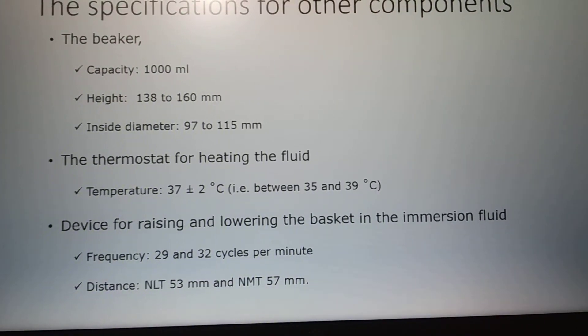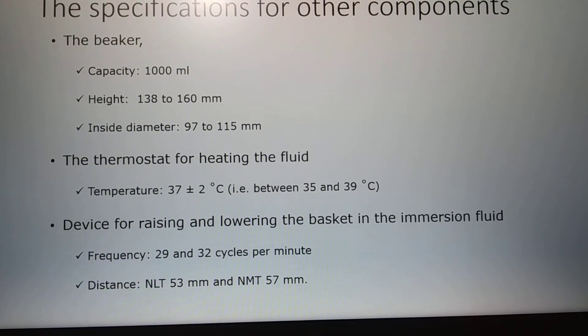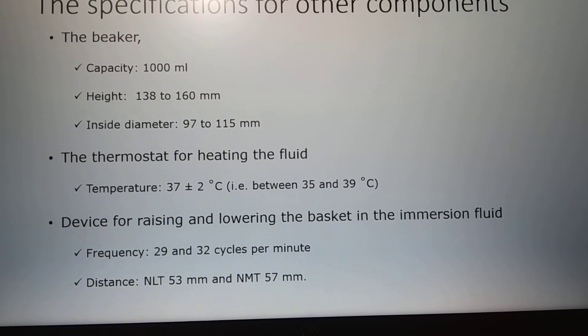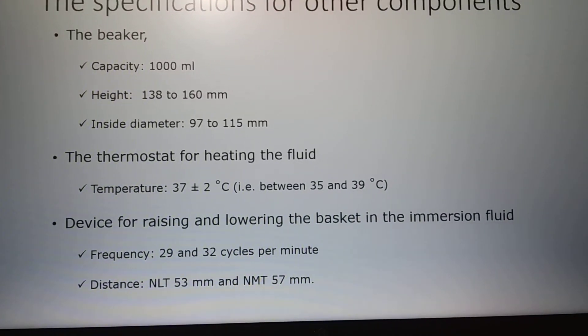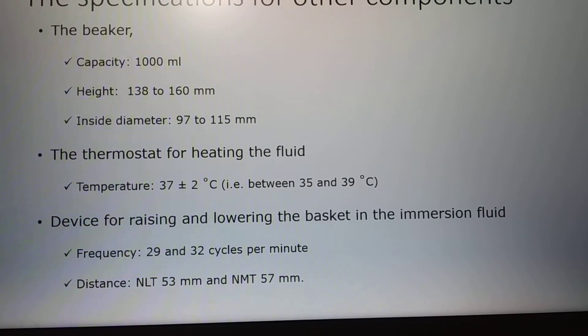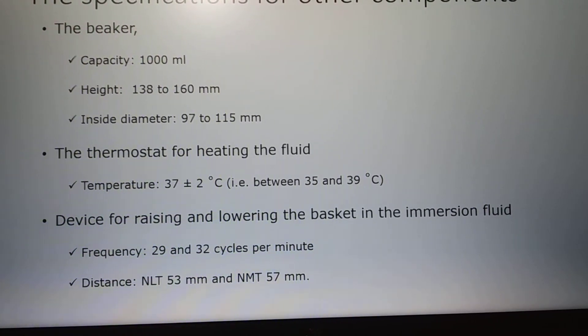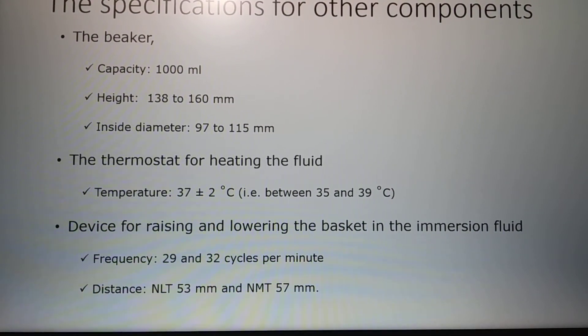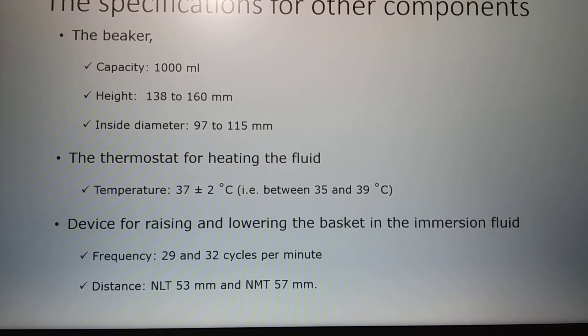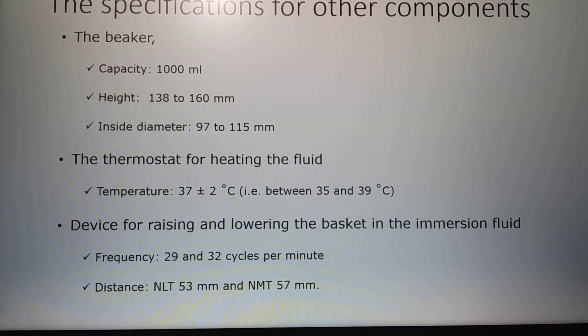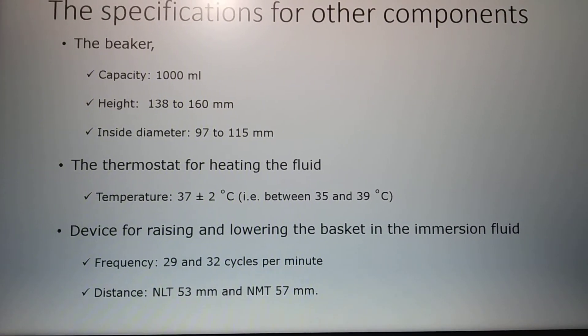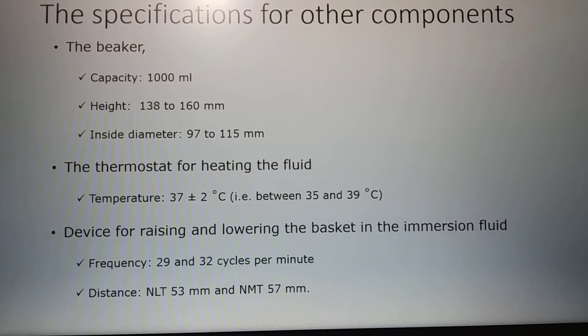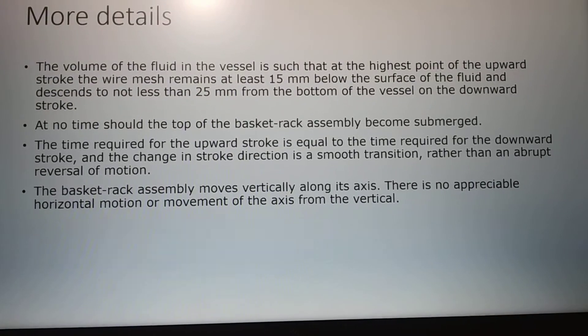The third part of the apparatus is a device that helps in raising and lowering the basket in the disintegration media. The frequency of operation should be 29 to 32 cycles per minute. The distance traveled by the assembly should be not less than 53 mm and not more than 57 mm.